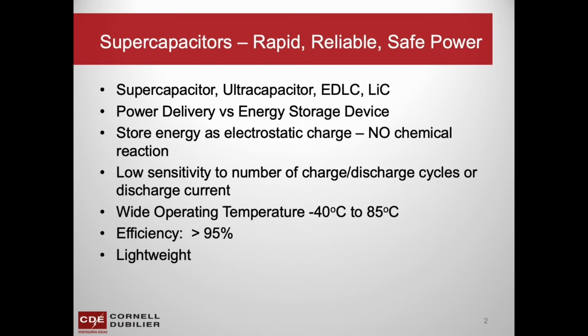The energy provided by supercapacitors is stored electrostatically with no chemical reaction. So in supercapacitors, the electrically charged ions are moving to the plates with no chemical reaction, allowing for little loss. In batteries, however, the ions have to be exchanged over and over again, and this can create loss and inefficiencies and lower life. Supercapacitors also have an operating temperature range of -40 to +85 for EDLC types and -25 to +85 for hybrids. Batteries cannot be used in this operating range at all, and for high temperature range, are significantly lower than supercaps, as mentioned before, about +55 C.